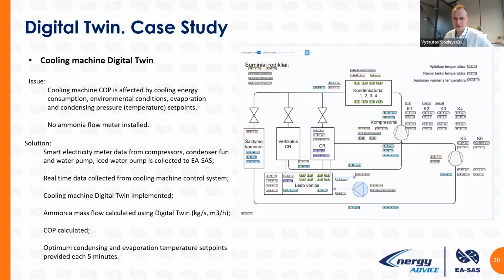We don't have flow meters at all, but the client has installed an electricity meter on the compressor side, on the condenser part, and on the pump side of the chilled water side. And the digital twin's overall mathematics was capable of calculating the coefficient of performance of the machine, energy consumption, electricity, and cooling energy consumption, 3 megawatts for example in this case, and 687 kilowatts overall electricity consumption of the cooling machine. So no ammonia flow meter was installed, and the client didn't understand the real energy consumption. They probably had knowledge about the chilled water consumption because a meter is installed here, but absolutely no understanding of the cooling energy consumption in the -20 chamber.